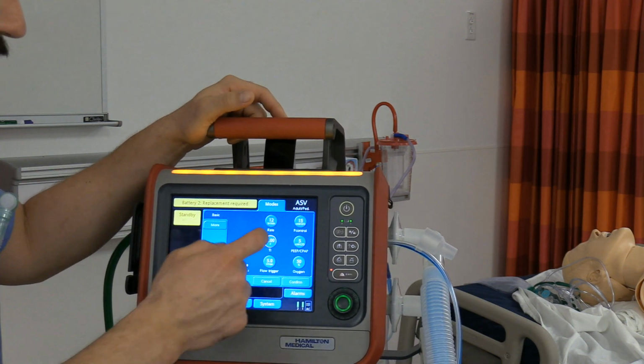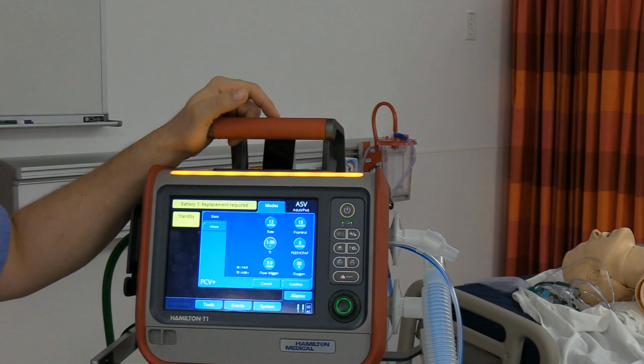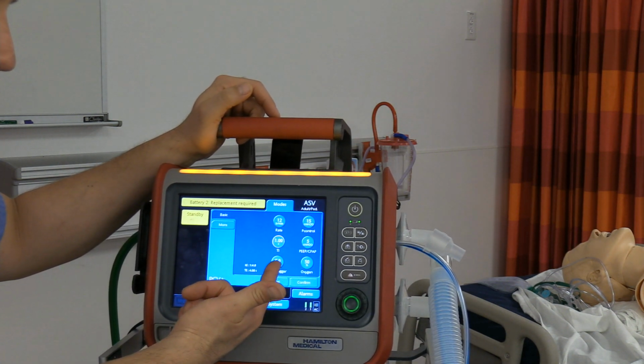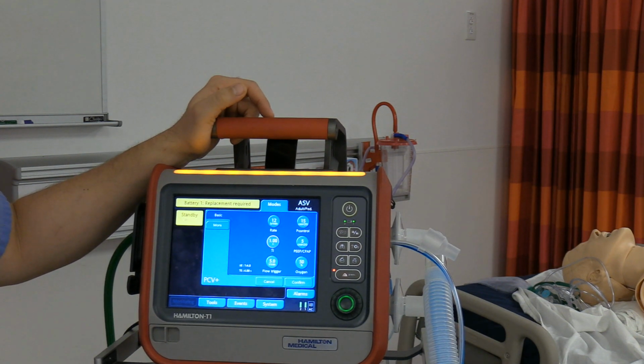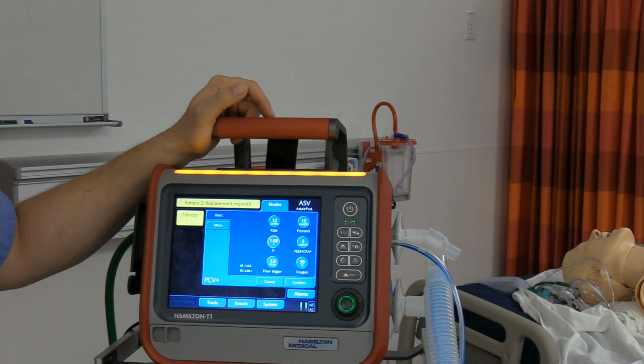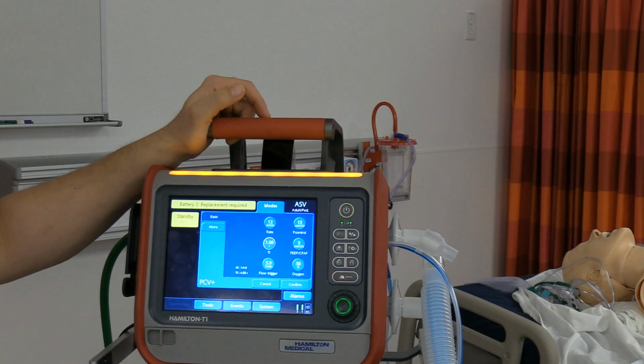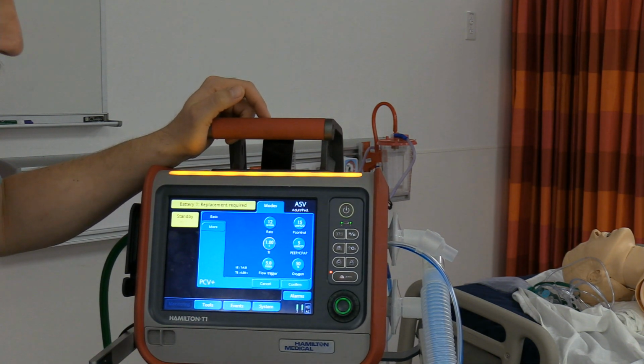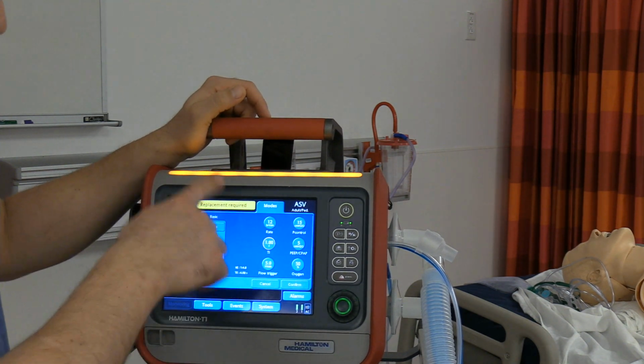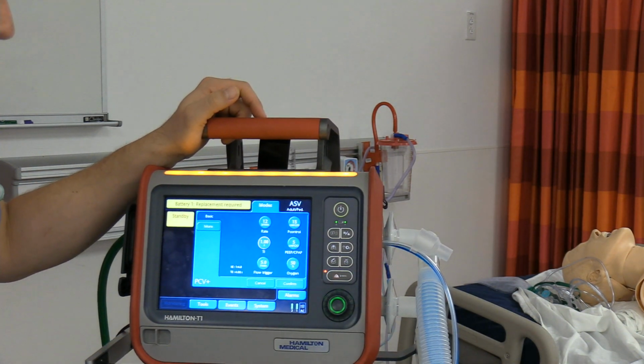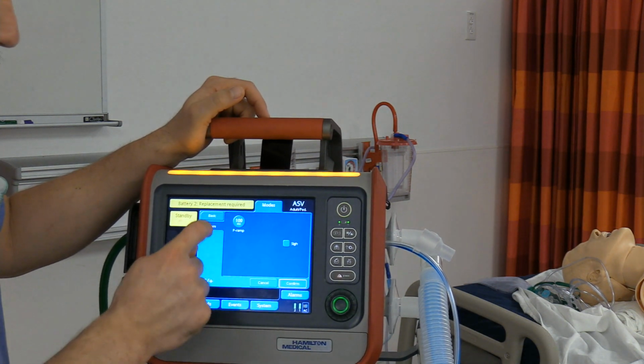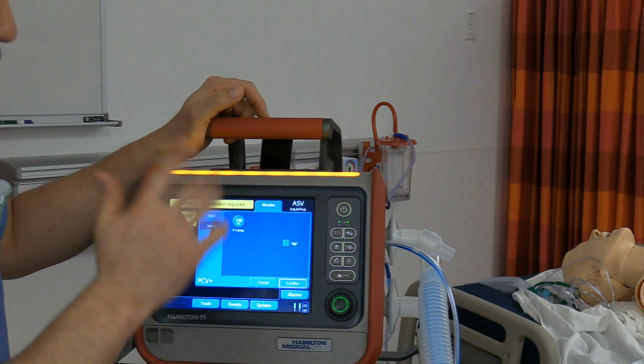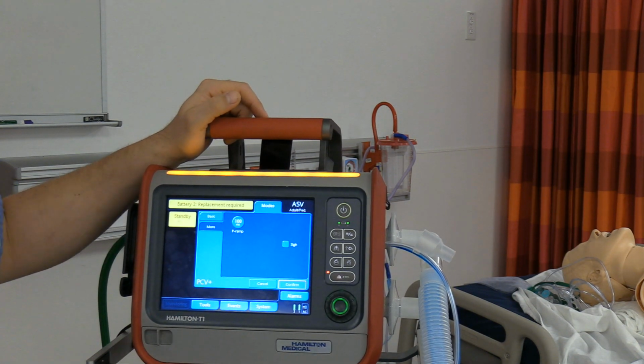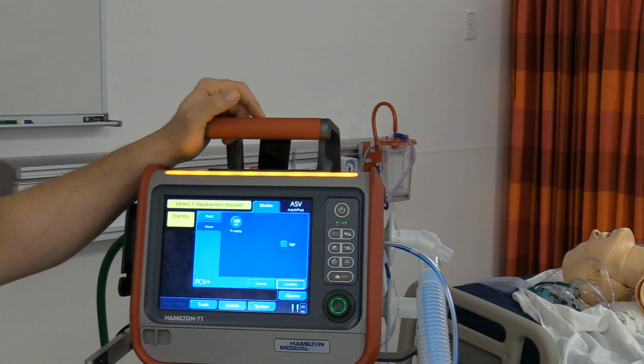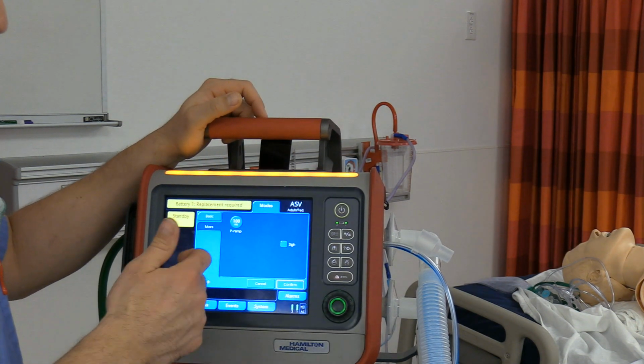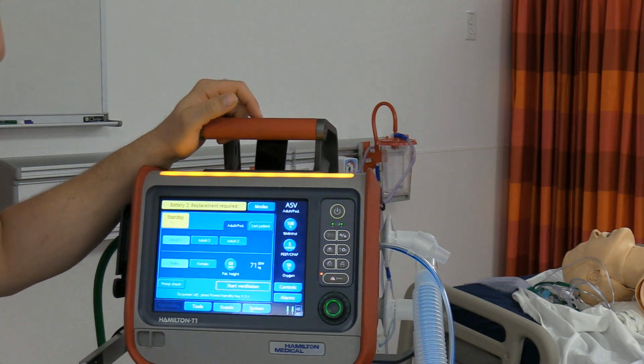Got a lot of different options. 1 second is typically a pretty good inspiratory time for starting out in pressure ventilation for our patient. A flow trigger of 5 is pretty good for adult patients on this, especially with the flow sensor being proximal. I've never had any issues with patients triggering. It shows you your I:E and your amount of E time here. The G5 and some of your other ones will show you a lot more information as you're changing rate and things like that. This one's a little bit more simplistic. If you wanted to hit more, you have the PSI feature, which we'll talk about later, and then ramp. Ramp is the same thing as rise, so it's how long we're taking to reach that pressure. Typically 50 milliseconds or 100 milliseconds is pretty good, and we'll learn to refine that with graphics later on.